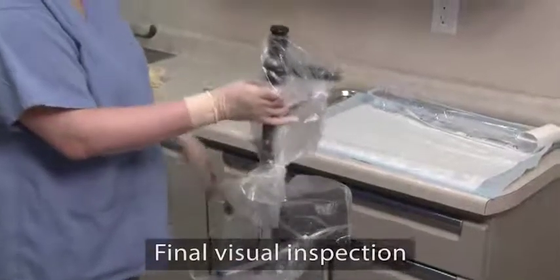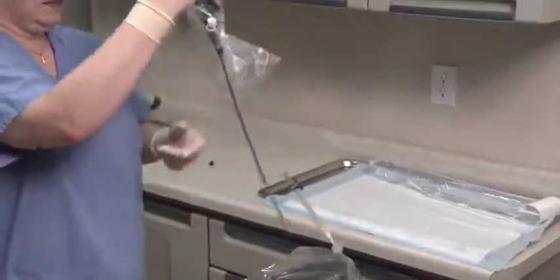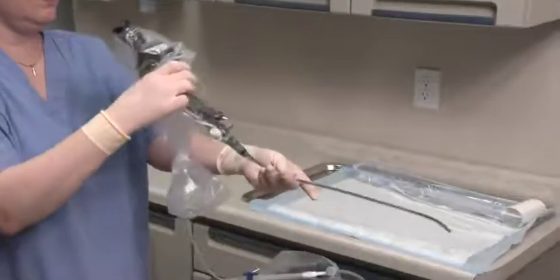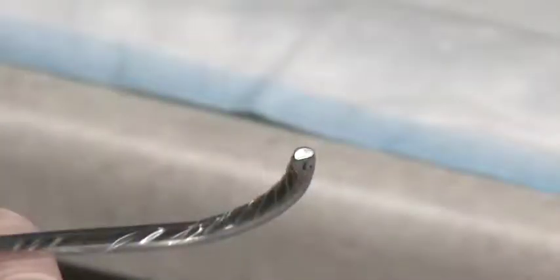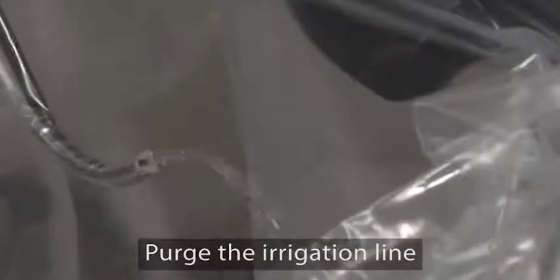Lift the system out of the installation stand. Also, visually inspect the sheath to make sure that the distal tip of the cystoscope is flush with the sheath window. Activate the flow control valve to ensure proper operation and fluid irrigation.